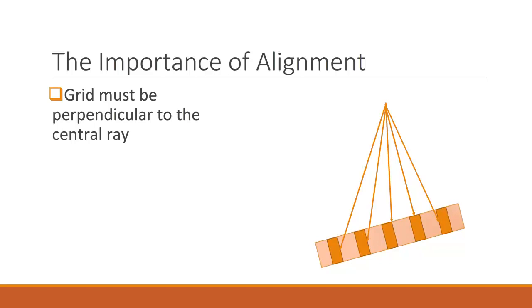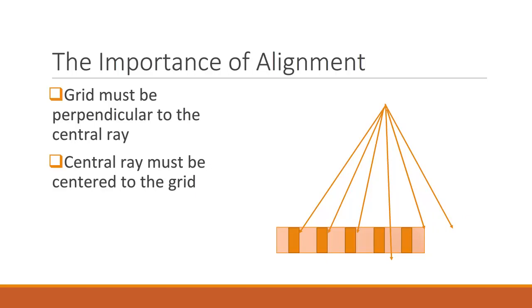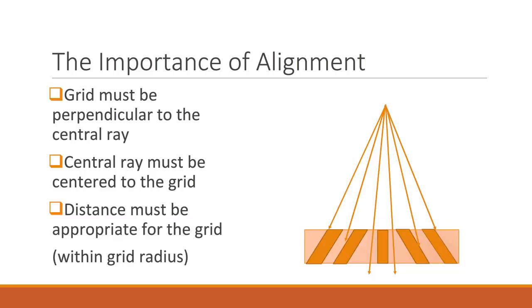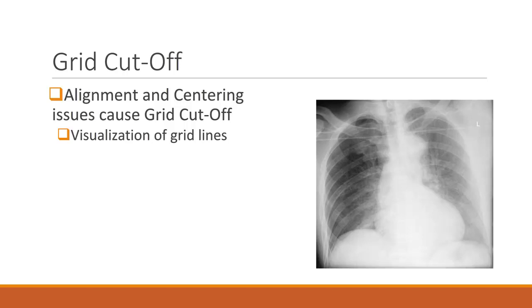Grids require a certain amount of precision to be used effectively. When alignment is incorrect, grid cutoff is the result. The first rule in using a grid is that the central ray and grid must be perpendicular. Additionally, the central ray must be directed to the center of the grid. The divergent x-ray beams interacting with the lead strips will be absorbed otherwise. The source-to-image distance, or SID, must be appropriate for the grid — meaning the SID needs to be within the designated grid radius. All of these alignment issues cause grid cutoff, where the necessary remnant beam is being absorbed by the lead strips and information is missing as a result.